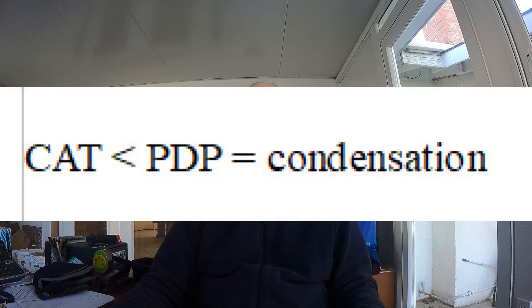So let's look at an equation that basically tells you how this works. If the CAT is less than the PDP then condensation occurs. The greater the temperature gradient between CAT and PDP, the faster the condensation will occur. Once condensation starts to occur, the water that comes out of solution must coalesce onto a surface. The longer the air comes into contact with a surface the more water will be condensed — I will refer to this as the dwell. So the condensation rate is a function of the temperature gradient.